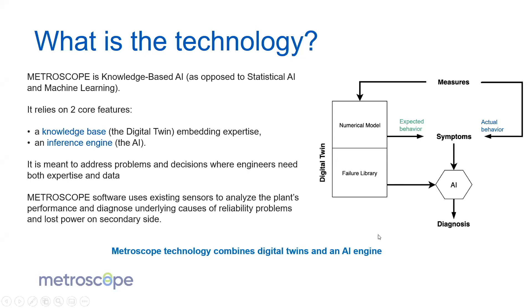On the right here you have a synthetic view of how we work. Everything relies on the measurements we get from the plants. We feed the measurements to a numerical model of the plants — that's what I'm going to talk about today. From that, we get an expected behavior that we can compare to the actual behavior from the measurements, and we get symptoms. At Metroscope, we go one step further: we want not only to find symptoms, but to do root cause analysis — going back to the cause of a symptom and being able to tell our customer that, for instance, there is a leak in a valve or a heat exchanger that's not working correctly, and then maintenance can take over.